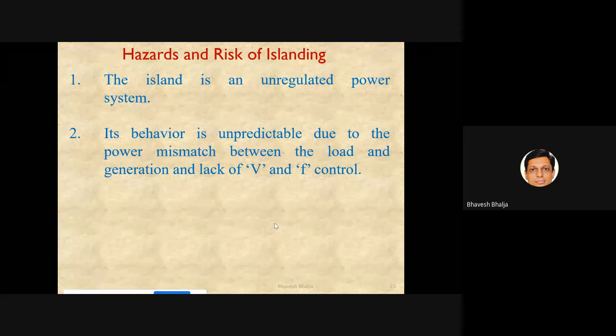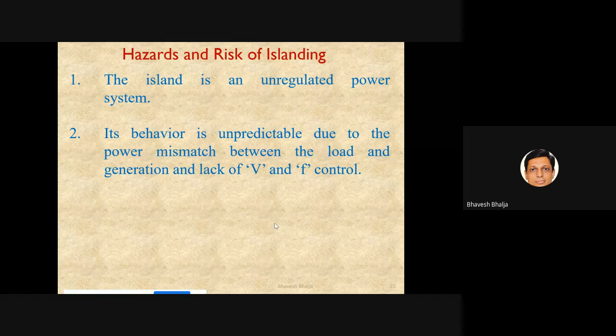As soon as islanding occurs and the island is formed, the small portion in which the DG is supplying power to the local loads has no control of voltage and frequency. Voltage and frequency control is possible only when the location where you have installed the DG has voltage and frequency control features.